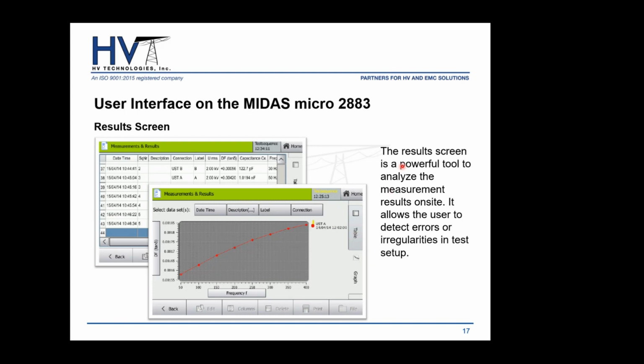And again, this is just a good, powerful tool to analyze your measurements on site. You don't necessarily have to transfer it to a USB and put it into your Excel spreadsheet. You can do it on the instrument on site. And then later on, when you have a little bit more time, you can sit and do a further analysis at a computer. This will also help you gauge whether or not there have been any errors in your test setup. So if you have different measurements that look off, then it's easy in the table, for example, to note that difference quickly and maybe run a test a second time to verify.